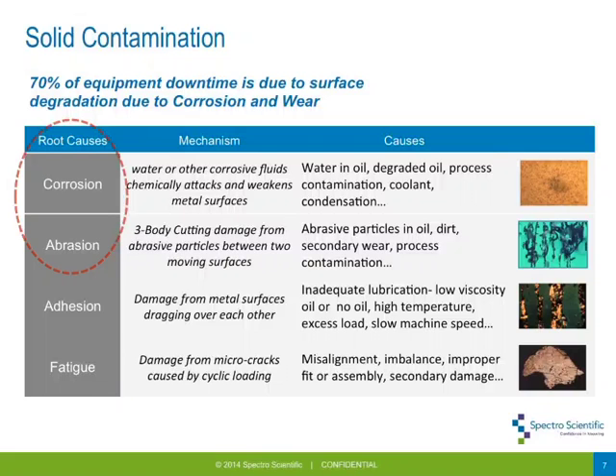Let's go to the most common types of contamination. When we talk about solid contamination, we're referring to particles that get into the oil. The most common is sand and dirt getting in, which can lead to abrasive wear, 3-body damage, and wear debris. You could also have debris generated as a result of corrosion from degraded oil, or soot contamination. The key takeaway is that 70% of equipment downtime is due to some form of surface degradation from corrosion and wear particulate, making it often the first point of contact for contamination control programs.